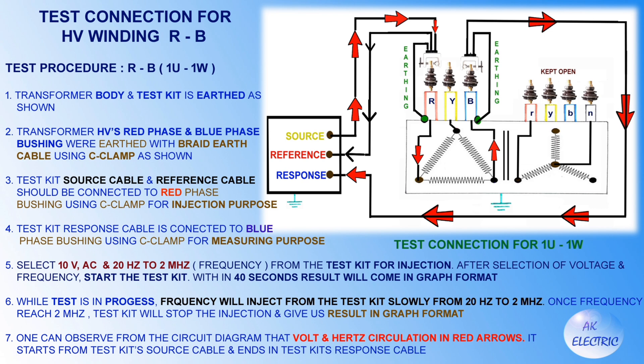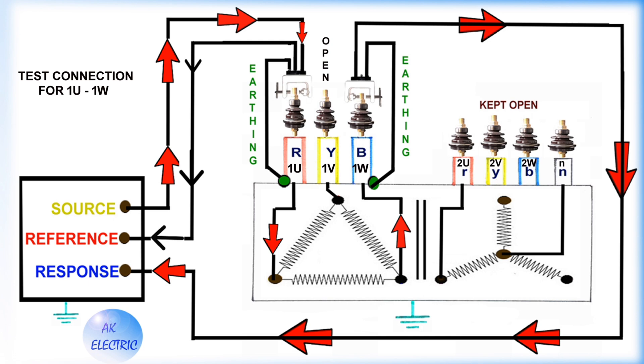For the HV winding R-to-B test connection: the transformer body and test kit are earthed. The transformer HV red-phase and blue-phase bushings are earthed with braid earth cables using C clamps. The source and reference cables are connected to the red-phase bushing using a C clamp for injection, and the response cable is connected to the blue-phase bushing for measurement. Select 10 volt AC and 20 Hz to 2 MHz, then start the test kit. Within 40 seconds the result comes in graph format. The frequency circulates as shown by the red arrows in the circuit diagram, from the source cable to the response cable.